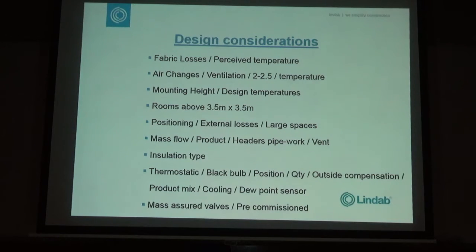And it's important to be able to do that, because if you design a radiant panel system, and I see them all the time, you'll get some documents from a client and he'll say, I want winter temperature 21 degrees plus or minus one degree, and you design to 21 degrees, and put a radiant panel system in, which is really 18 degrees, but that means with 3 degrees on top of your 21, it's actually going to be 24, so you'll overheat in that space. So when you're controlling it, you really want to be able to use that 3 degrees so you can take that off and not overheat the space, because it'd be stuffy.